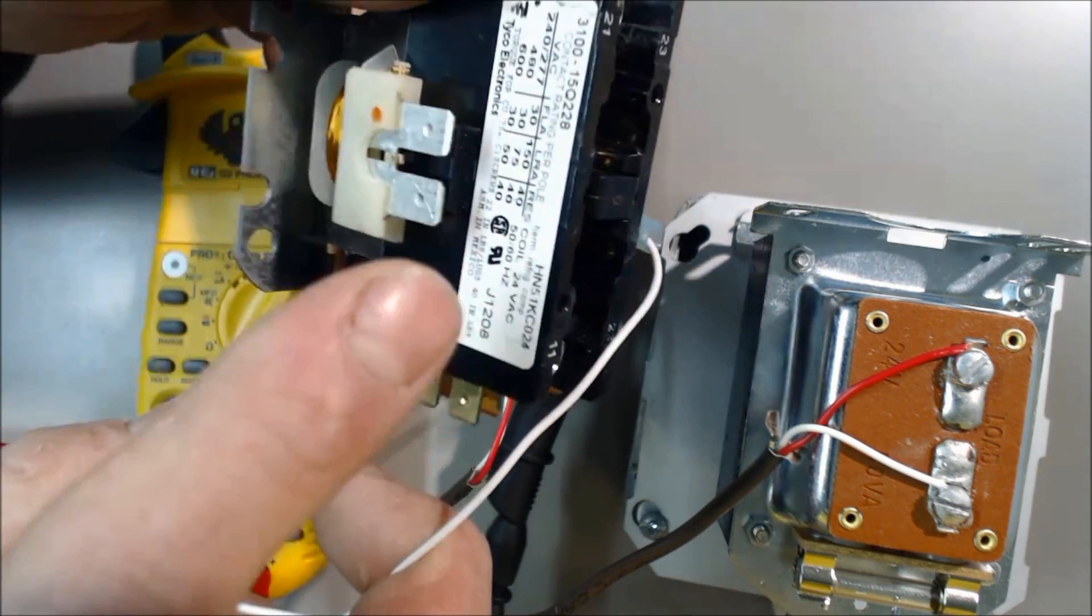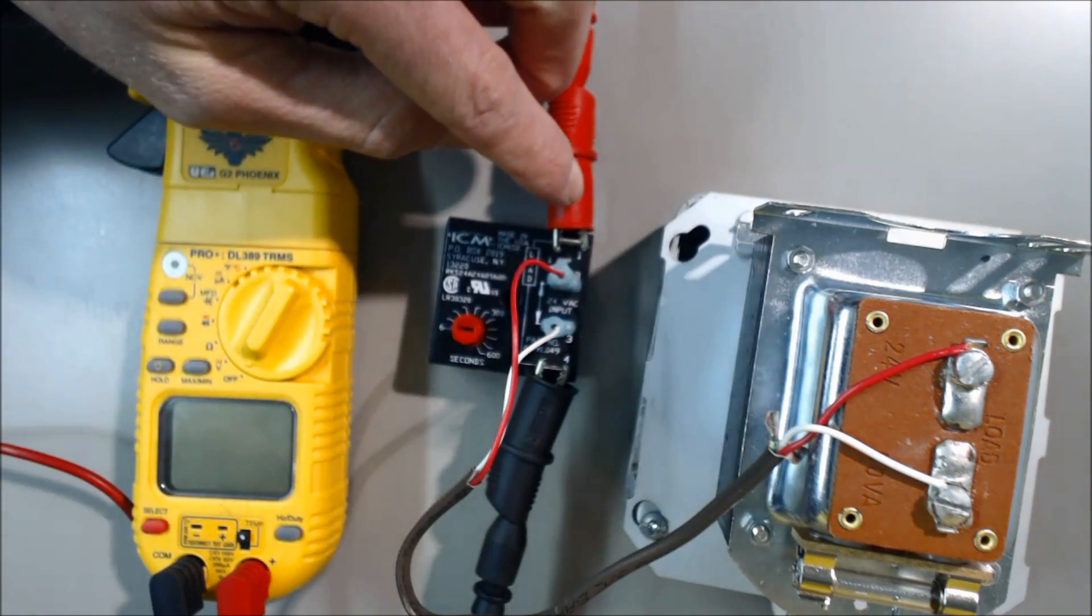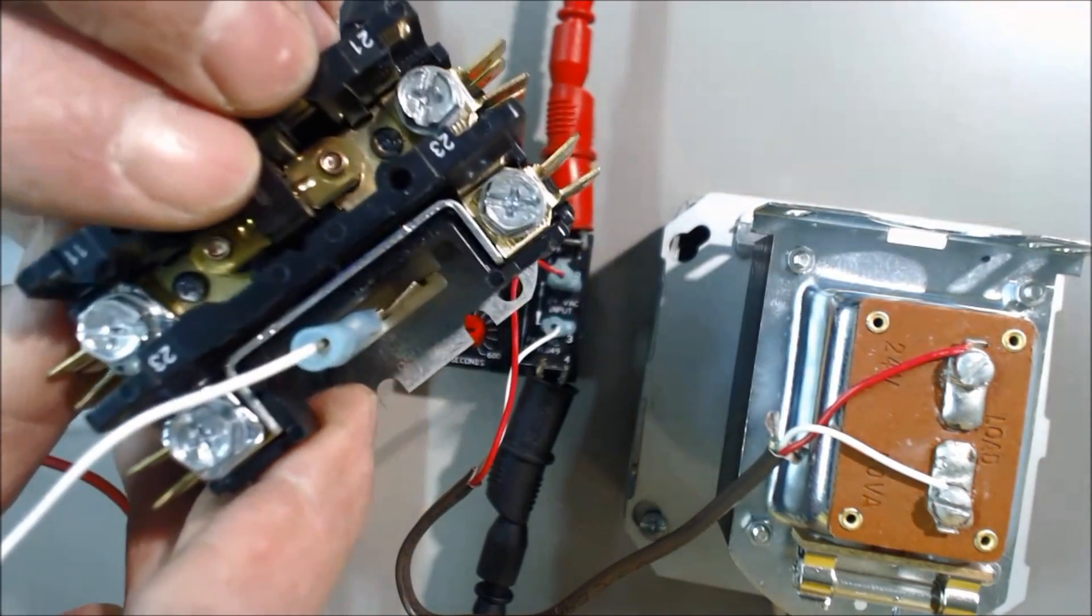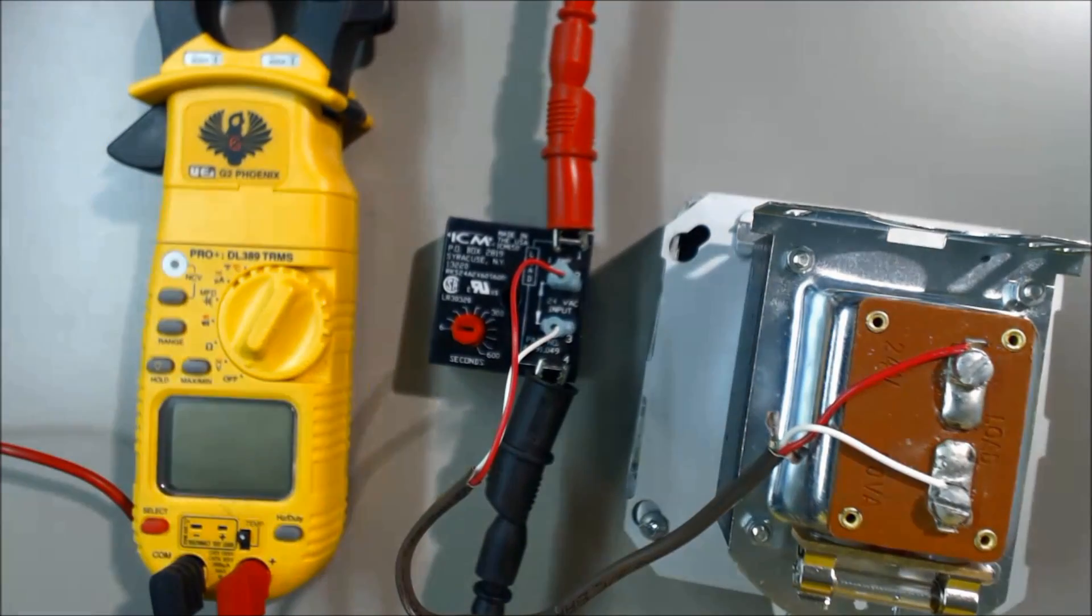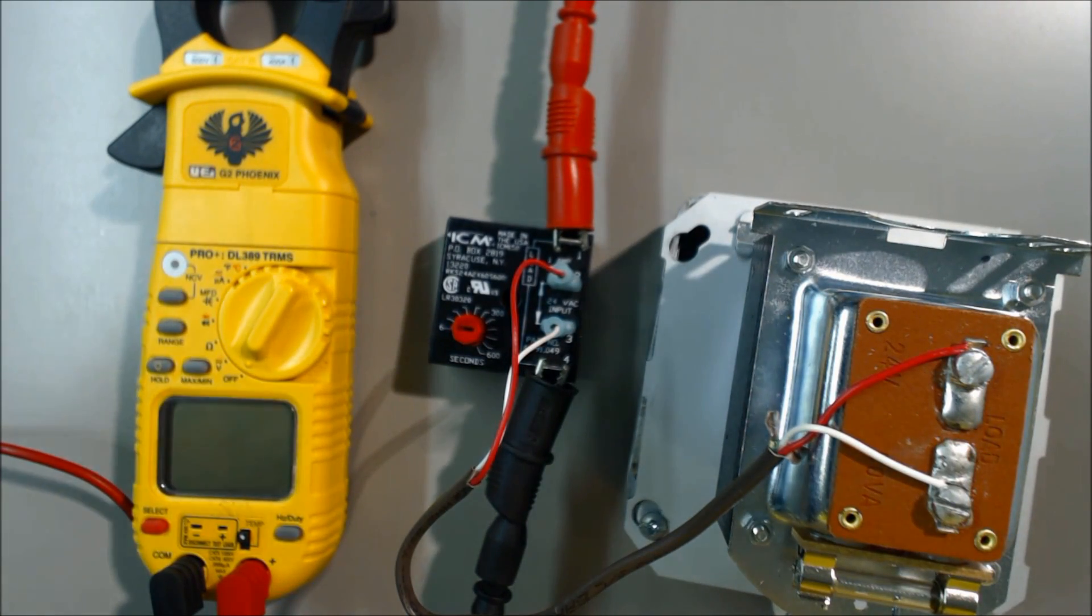What you have then is this side would be your common, that would get jumpered to there, and then you have your hot, which will be coming out of here. It first comes in here, then comes out, and then you can wire it to your contactor. What that'll do is it'll wait six seconds before this sucks down. That's it. Find us again at acservicetech.com.